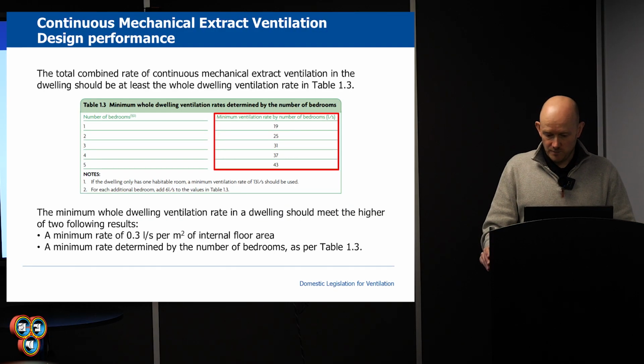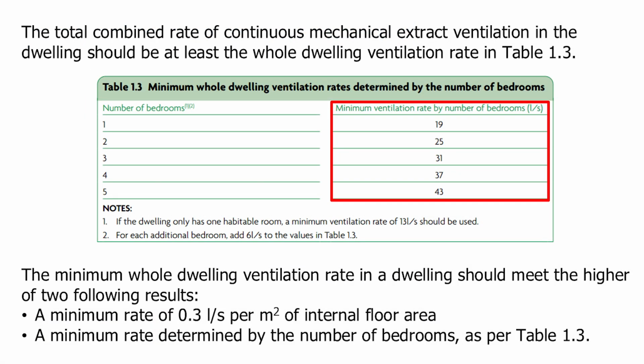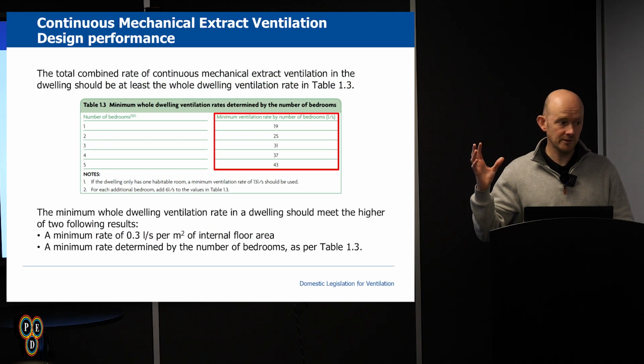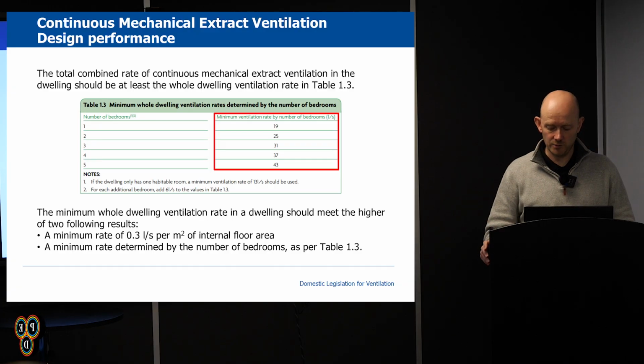Continuous extract rates must be calculated in 2 ways, and the larger of the 2 volumes will be used. Step 1 is to obtain the rate from the number of bedrooms. Step 2 is to multiply the total floor area of the property by 0.3 litres. Should the continuous rate be higher than the minimum high rate, then the continuous rate should be used for the boost as well. There is no need to increase the speed to give any additional boost. However, depending on various factors, lifestyle, HMOs, where you've got lots of people, you might want to increase it.